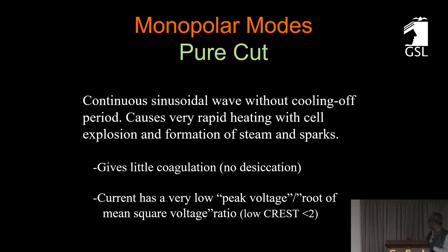Now in monopolar, there is another mode that is called pure cut. It is a continuous sinusoidal wave without a cooling off period, causing very rapid heating with cell explosion and formation of steam and sparks. It gives little coagulation, there is no desiccation, and the current has a very low peak voltage.